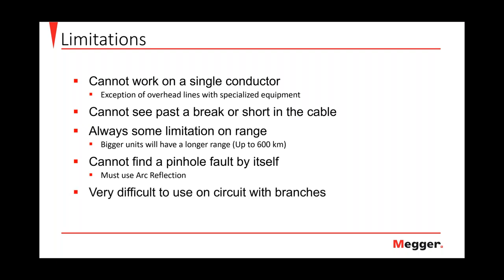They're also difficult to use on circuits that have branched conductors. So anywhere where there are taps, it's going to be difficult because now we have multiple parallel paths that the signal would have to go on. So it's much easier to interpret the traces that we see in the results of this unit when it is one single circuit that we are checking with no taps.